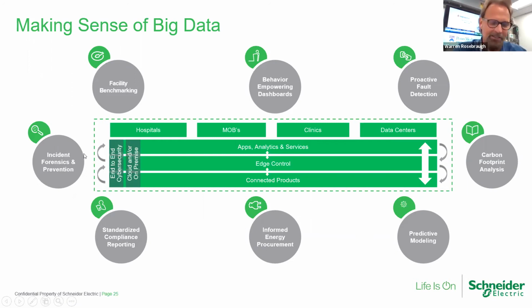Today we have analytics around our Square D power equipment. I can start to look at an oil-filled transformer and look at real-time oil samples that give you temperature, humidity, and gases released in the oil if you have an arc flash or potentially an arc flash in that transformer.